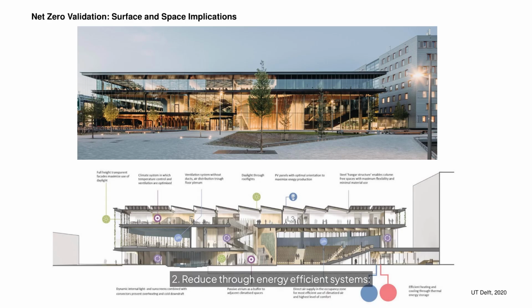The building also uses an underground thermal storage system to efficiently regulate indoor climate, further reducing reliance on active mechanical systems. Space is conditioned through direct air supply in the occupied zone for most efficient use and highest level of comfort. Dynamic lighting and sunscreens combined with convectors help prevent overheating and cold downdraft.